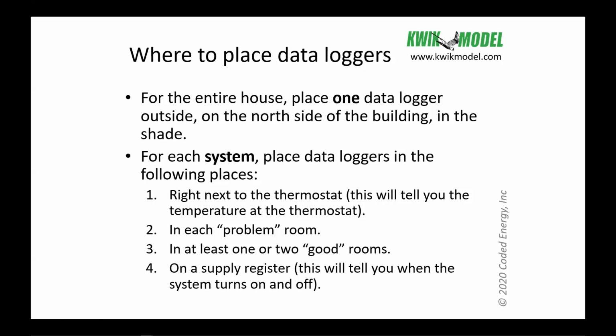Then the other one that's very important is you put one directly taped to the face of a supply register. You take one of those data loggers and you put it right on that supply register so that when the air conditioner turns on, that data logger will sense that really cold air suddenly coming out of that register and it will drop very rapidly. And then when the system turns off, it will start to rise very rapidly. And you can see that. It'll tell you exactly when the air conditioner turns on and when it turns off, okay?